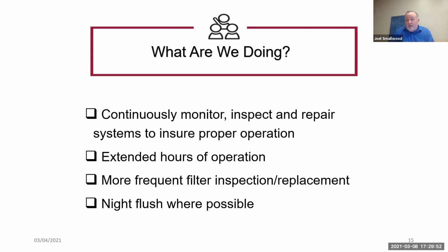We're also doing more frequent filter inspections, which we're already doing, and then more frequent replacements we're highly anticipating. Filters really have a lifetime based on how much they operate, outside air conditions, and how much dust there is in the air. So these inspections are certainly going to lead us to more frequent replacements, because we're simply running the systems harder than normal, for more hours than normal, forcing more outside air, all the things that lead to filters needing to be replaced on a more frequent basis. We're doing this in an effort to provide the best ventilation we possibly can into the building.